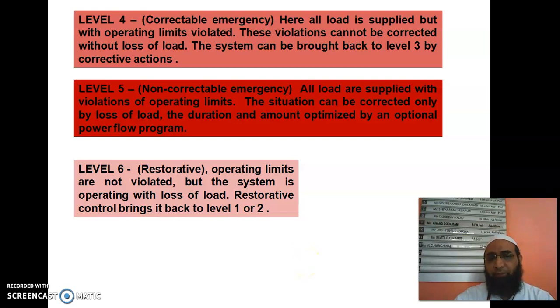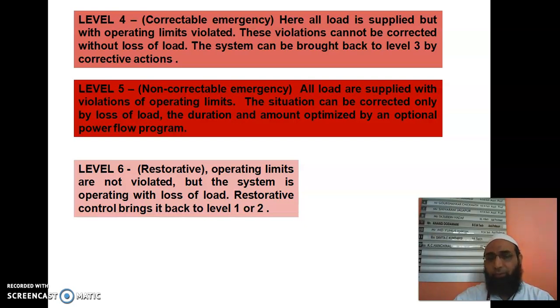Level 6 is the last level, also called the restorative level. Operating limits are not violated, but the system is operating with loss of load. Restorative control brings the system back to level 1 or level 2.